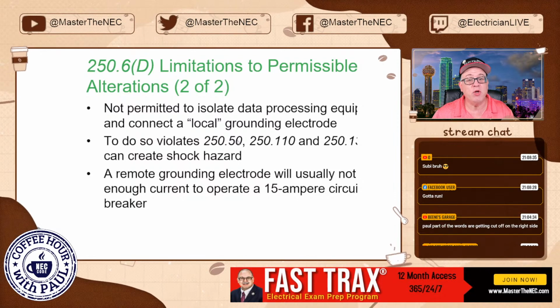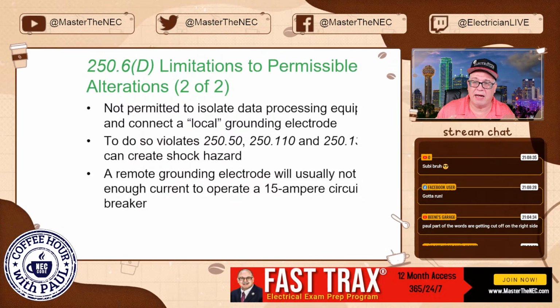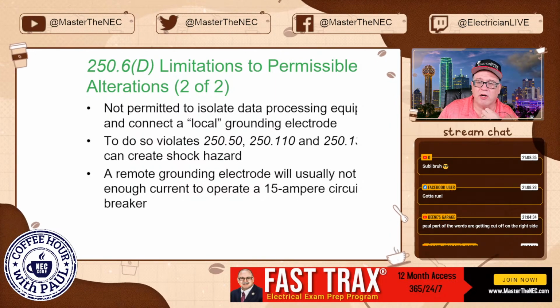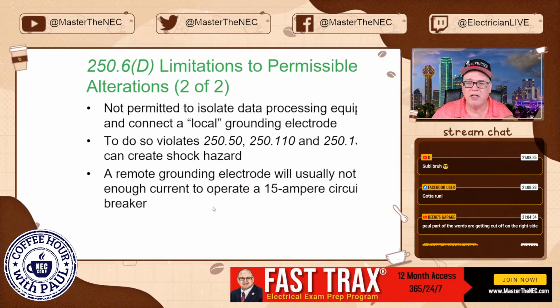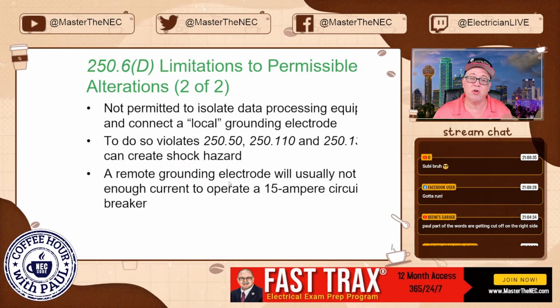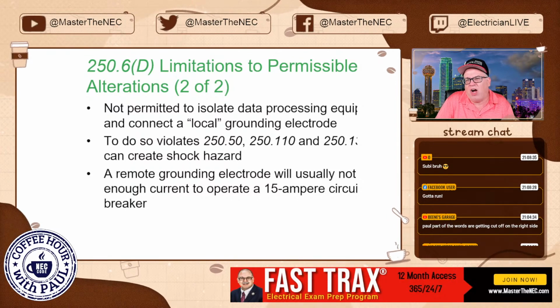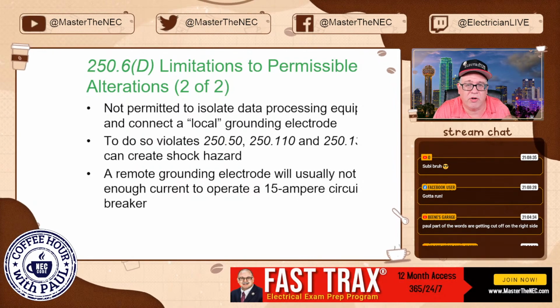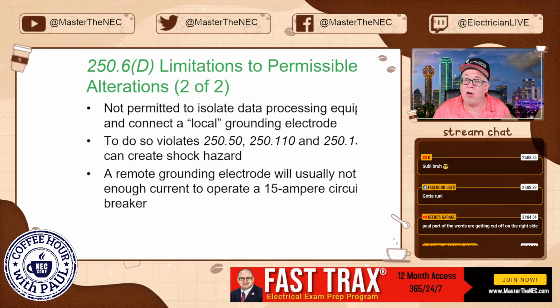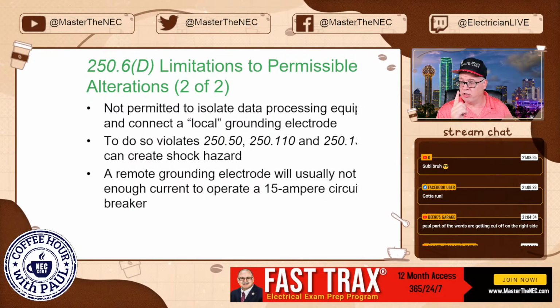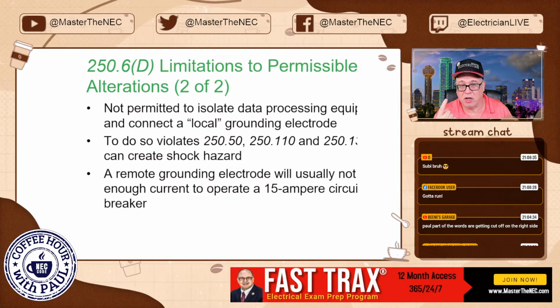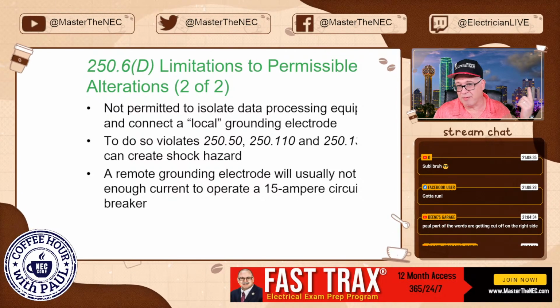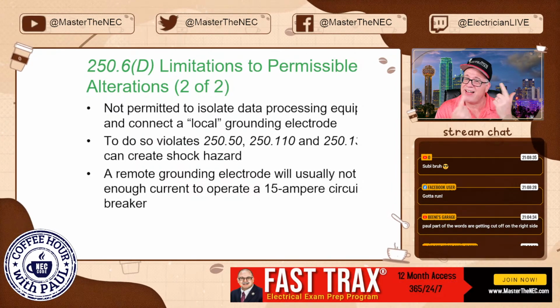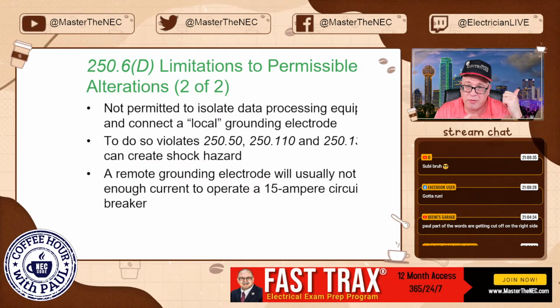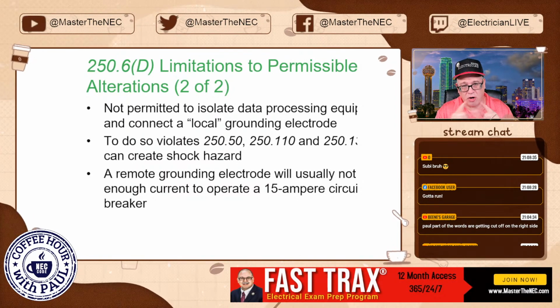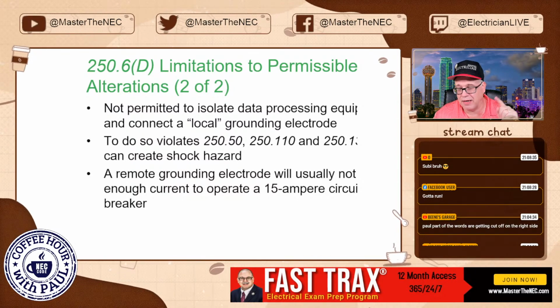All right, now if you did that and you said, well, screw it, because it's data processing and the noise, I'm not gonna run an equipment ground. Well, you know what? You're gonna violate 250.50, 250.110, 250.134, and in doing so, if you were to drive ground rods there and use that only as that source, one, you're not gonna clear overcurrent devices unless you have a short circuit. But secondly, now you've got two different earth potentials. You have the ground rod for that data processing equipment or whatever, and now you've got the raceway that supplied the power there or an equipment ground that came there. So you've got two different potential points because one goes back to the system's connection to earth, and now you've got another connection to earth, creating separation. Not good, okay? So we don't want to do that.